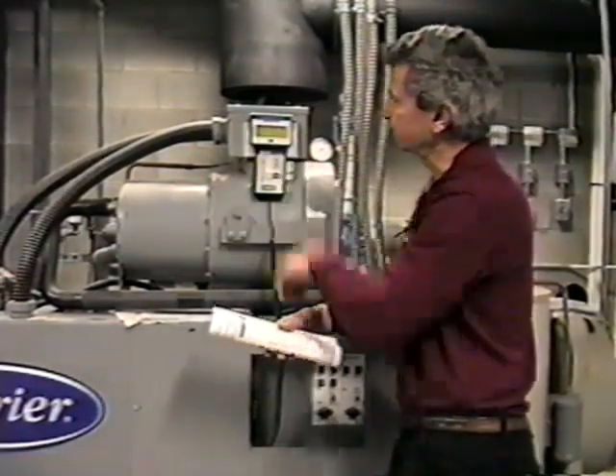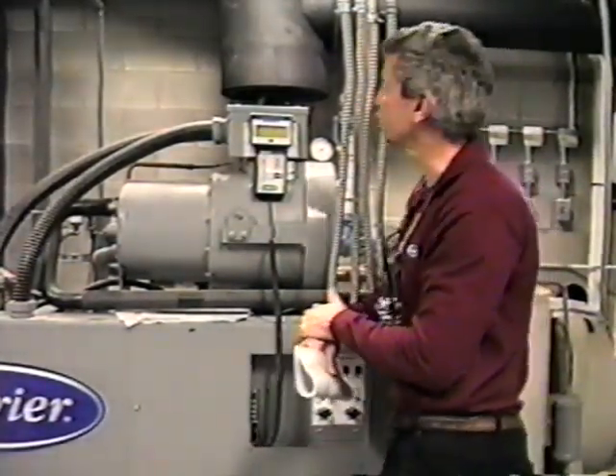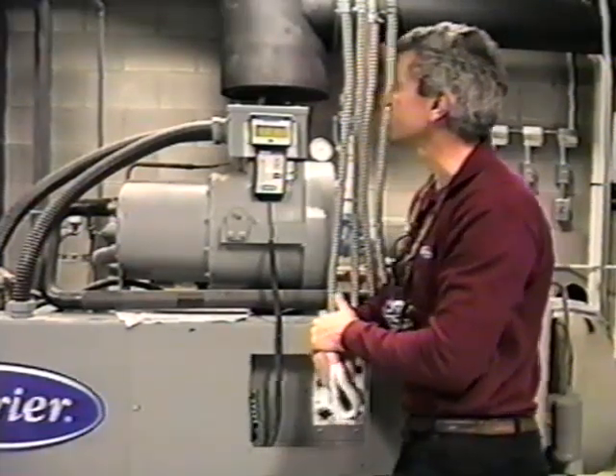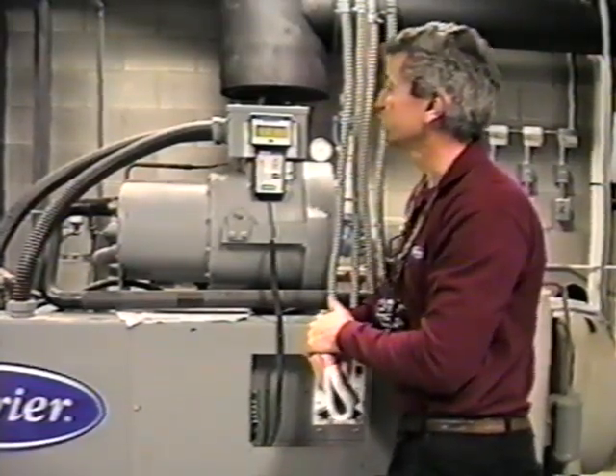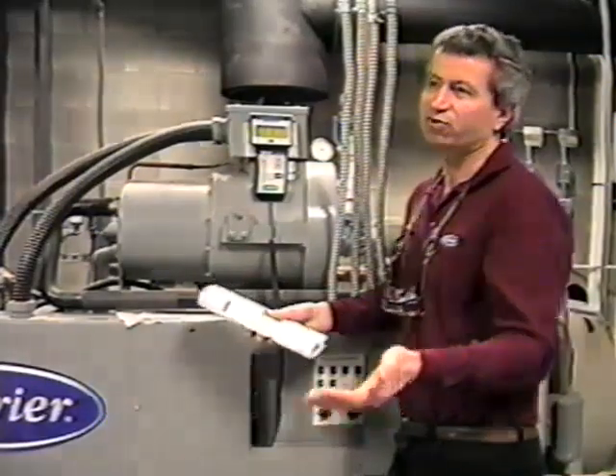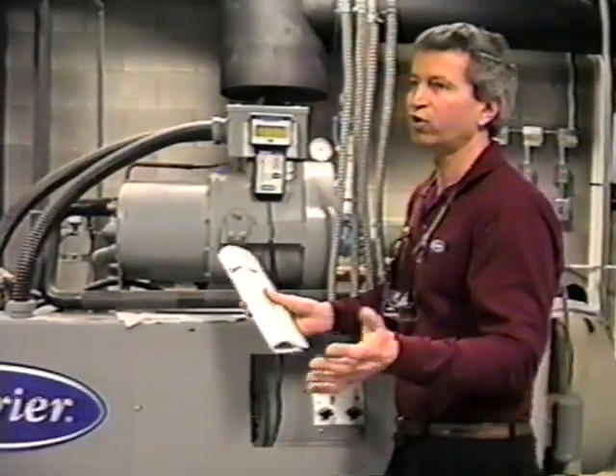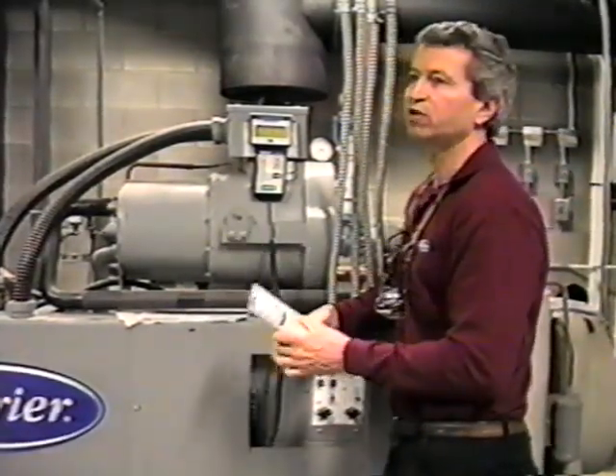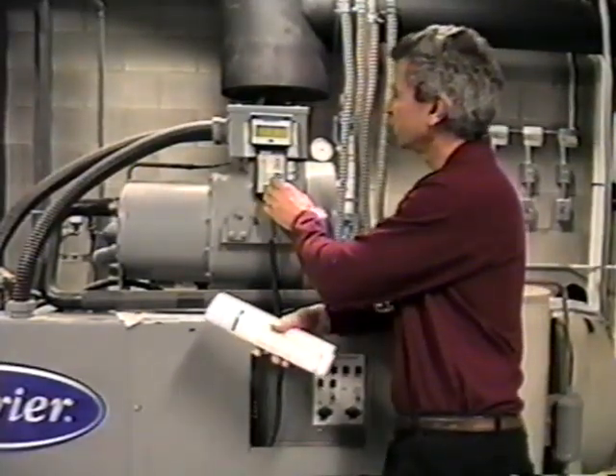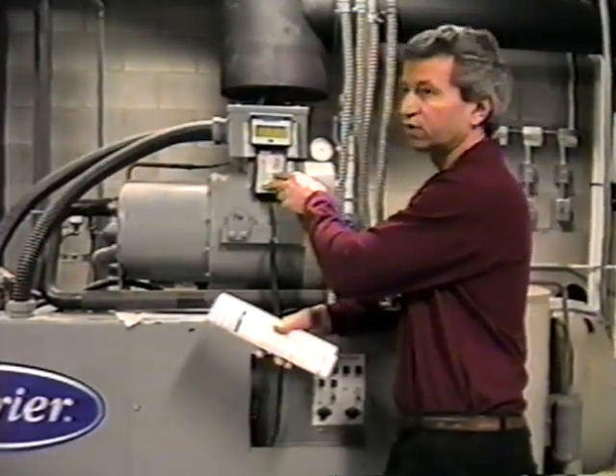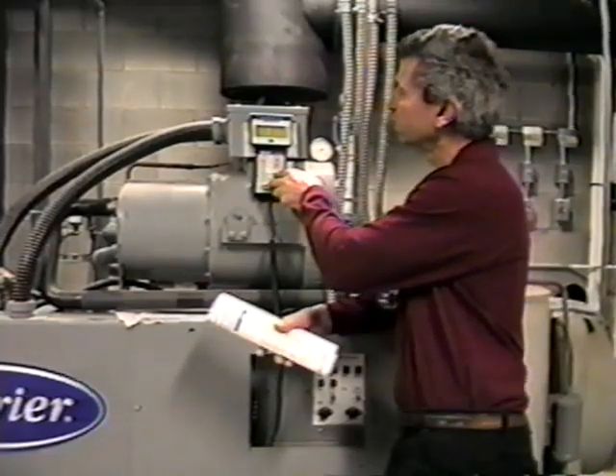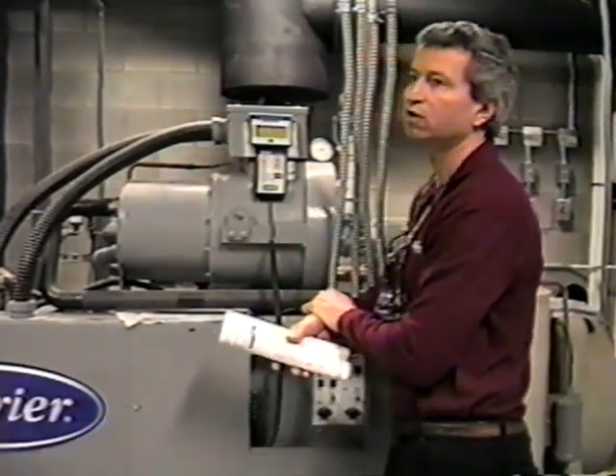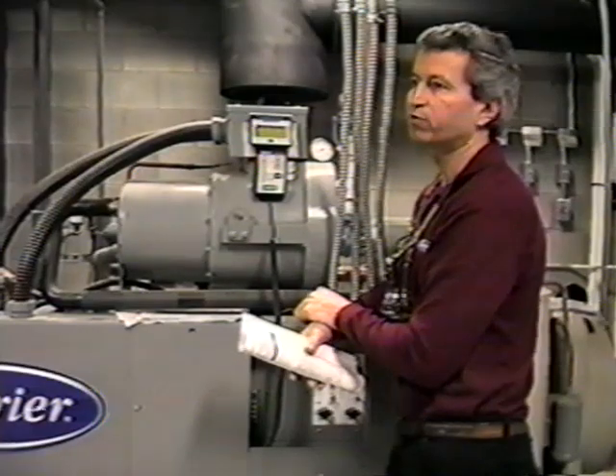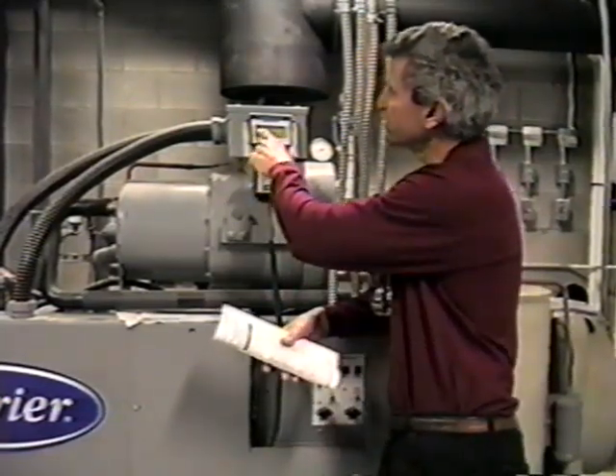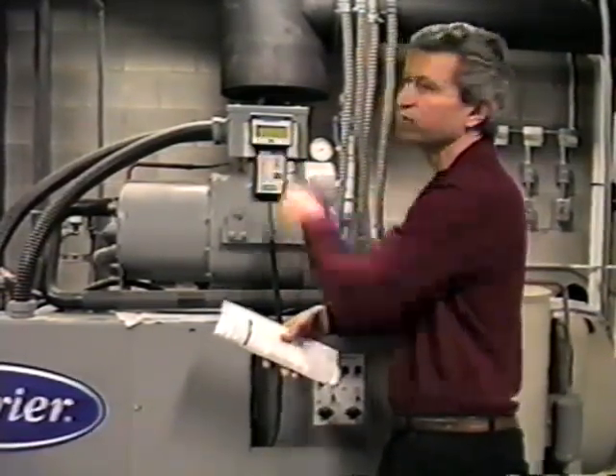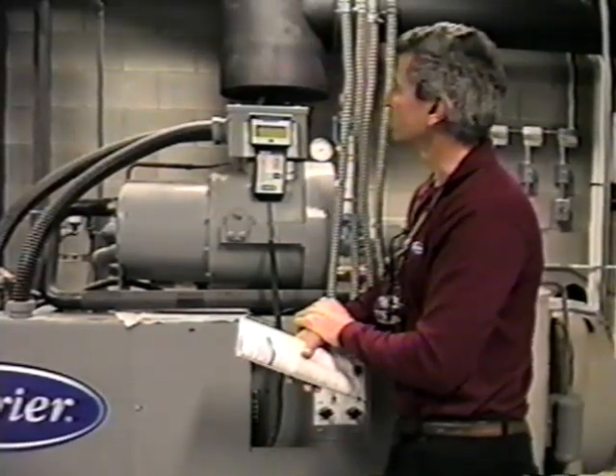Now you see a bunch of abbreviations. It says SCT.B, SST.B, SH.B. You can probably guess what some of those mean, but if you were unsure, you don't need to go to your manual, even though it's in there. At this point, if you just hit both keys at once again, it'll go into an expanded mode, and it'll read out in plain English what that temperature is. In this case, SCT.B is saturated condensing temperature.